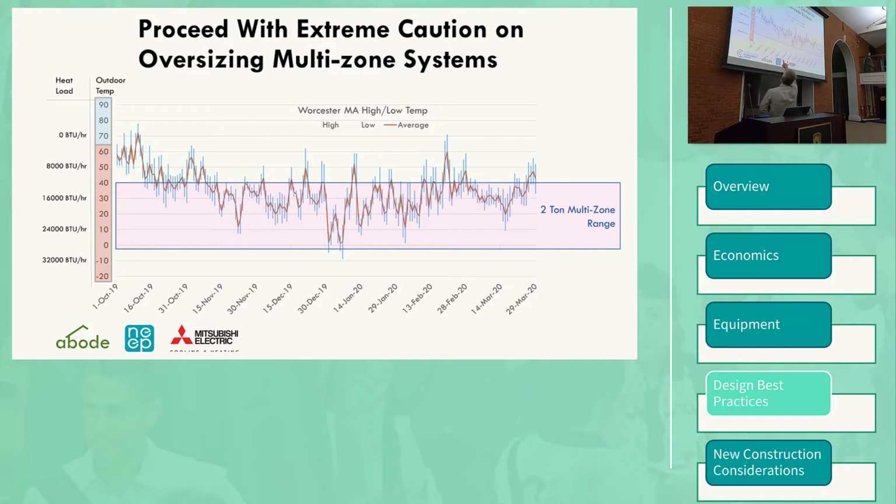But you can see that when it's above 40 degrees, that's the lowest. What's being represented by that top end of that rectangle is the lowest speed the heat pump wants to do. There are many different ways of representing this graphically, but this is a nice example because you can see the impact over the season. So from October 1st until you get to November, there's going to be a number of days where the unit cycles. Now, this is a 2-ton system. If you had a 3-ton system, you can see, oh my goodness, it's going to be flashing on and off all the time for this relatively low load home, a relatively small, relatively decent construction home.